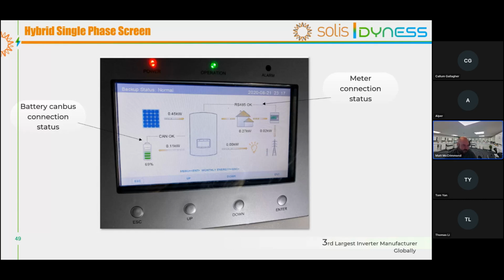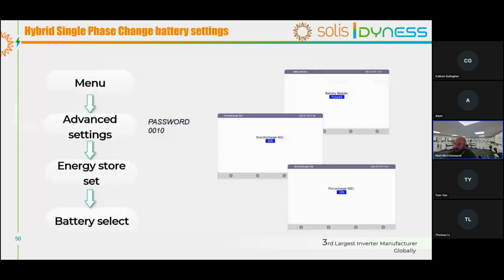So these are the kind of fault finding steps that we normally check based on just looking at that screen. Before you leave site and you've installed an inverter, make sure that screen is pretty accurate in terms of what you would expect it to see. If not, you can call our service line. We can go through that, but we'll discuss how you do that process later on. I did discuss that once you've set up the inverters, we probably don't want to actually touch the system.